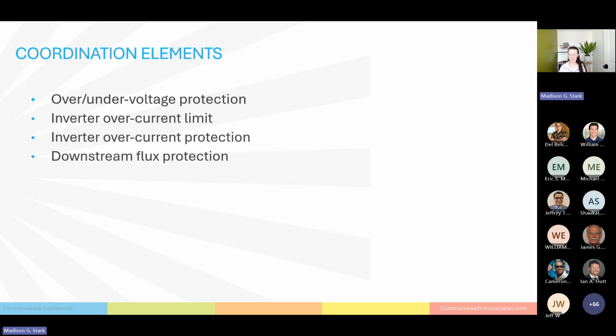Now, I don't know if you caught this, but when we went over the language of PRC 19, a lot of that verbiage really was geared towards synchronous generators. So the coordination elements that are described in PRC 19 for inverter-based generation are very limited. It's kind of constrained to over-under voltage protection, the inverter overcurrent limits and protection, and then you can include downstream flux protection for things like your generator step-up transformers, if you have any other auxiliary transformers in the system or anything like that.